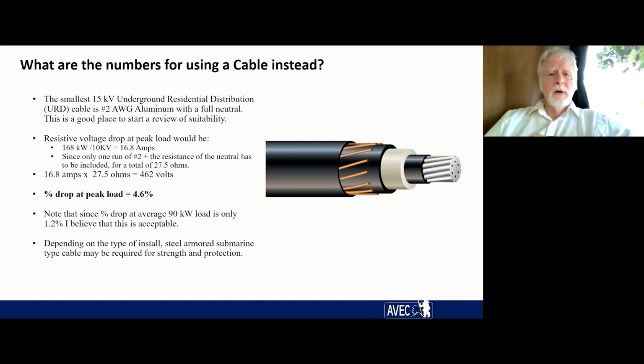There's different ways we could put this in. We can trench it. We could put it in a waterway. We can put it over marshy ground where in the spring when it melts it would sink down into the marsh and be lost. Some of these installations do require submarine cable rather than URD, but in terms of electrical characteristics, a URD cable is something that we use everywhere, and it's very well known, it's inexpensive, and it provides an interesting baseline for looking at the characteristics of it using DC.